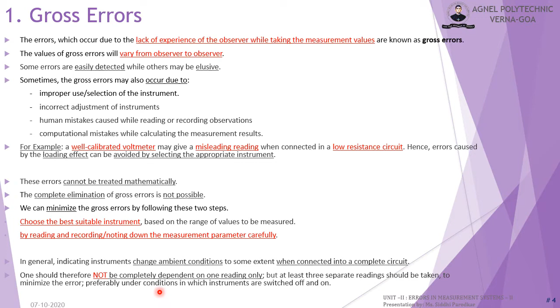These errors cannot be treated mathematically and also cannot be eliminated completely, but they can be minimized by first choosing the best suitable instrument based on the range of values to be measured and by reading and recording measurement parameters carefully. In general, indicating instruments change ambient conditions to some extent when connected into a complete circuit. Thus, one should not rely only on one reading but at least should take 3 readings, probably under conditions in which instruments are turned on and off.